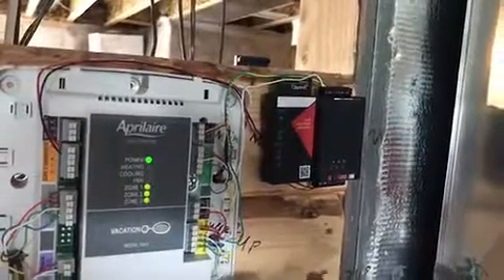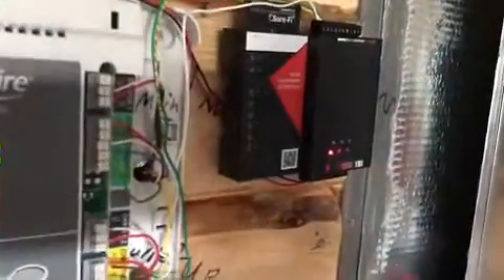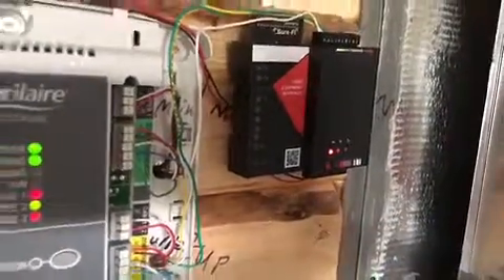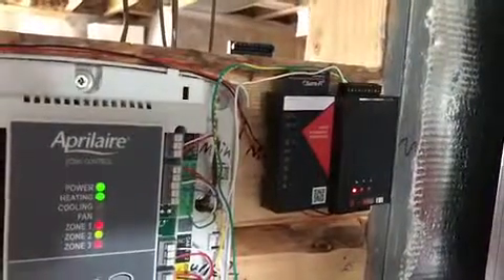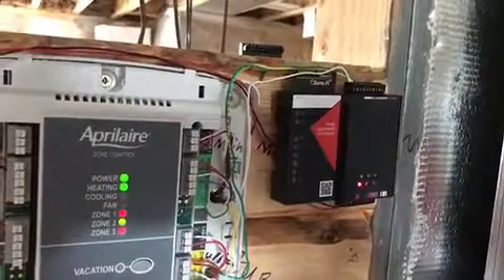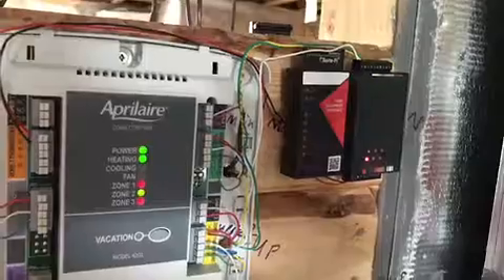Full communication, and it's up through kind of standard house things, but you know, a lot of vents and wood and tile and that kind of thing. Okay, you can now see as we activated the thermostat that it's calling for heat right here. And now we've got that working, we need to connect the analog bridge so that we can control the damper.